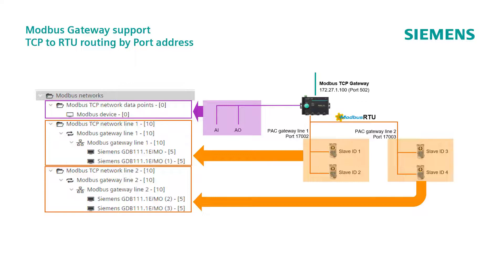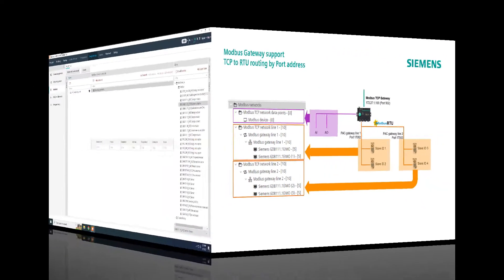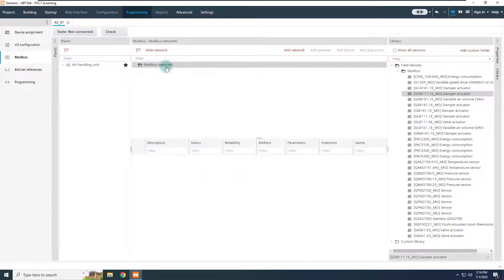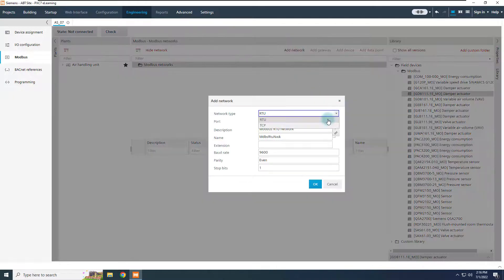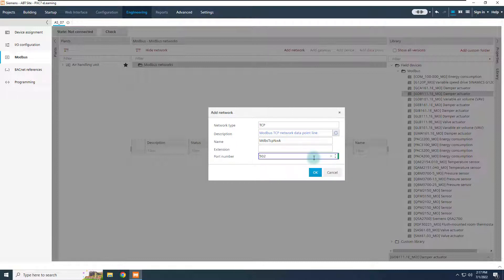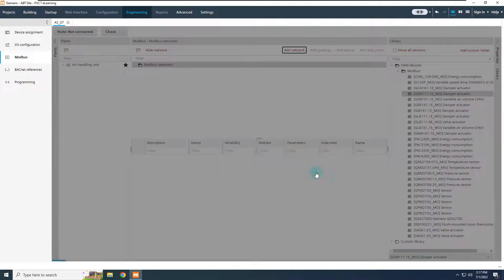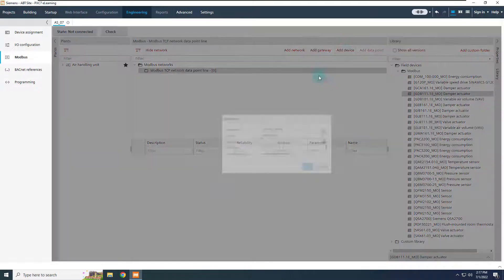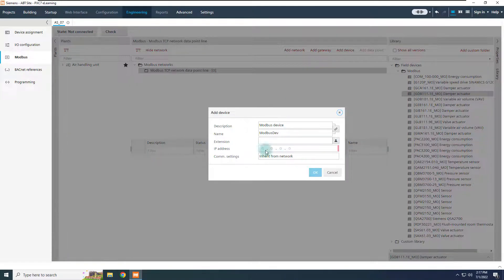Let's see now how to configure it on ABT site. Here we are again into the Modbus editor, from engineering of the controller. Add a physical TCP network for gateway itself, and change the port number, if necessary. 502 is the common port number for Modbus TCP networks, but it can be different for other devices. Please check this information with the Modbus gateway vendor.